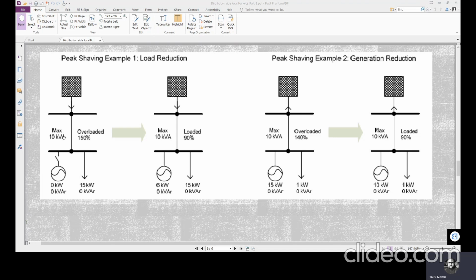Okay. Now 10 kVA is the maximum power carrying capacity of the line, but as of now it is 150% overloaded. And this generator is not connected. So there is a local load which is 15 kilowatts, so that is completely fed from the grid. So this is 150% overloaded. Of course, here we assume unity power factor. That's why we are able to compare kilowatts and kVA, and we can say that it's 150% overloaded.